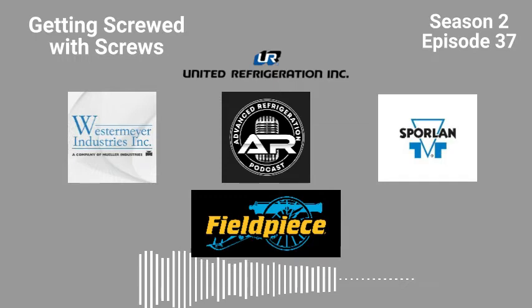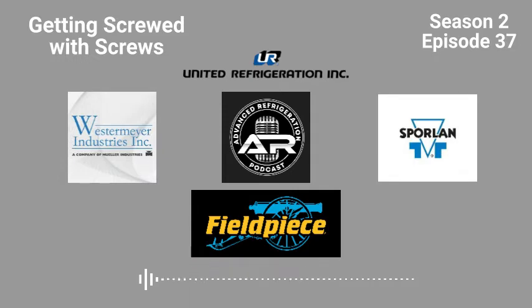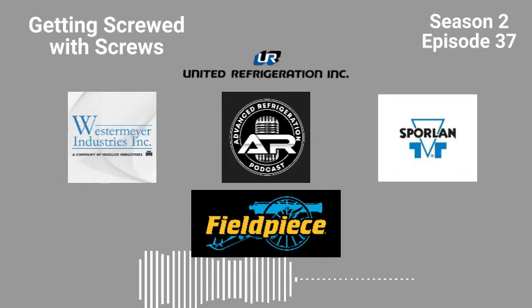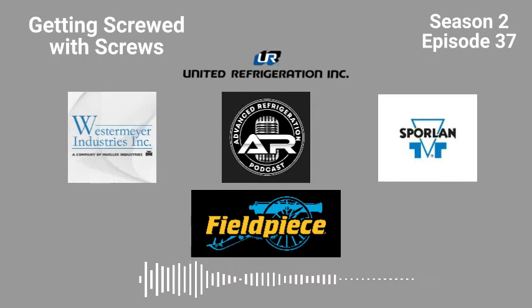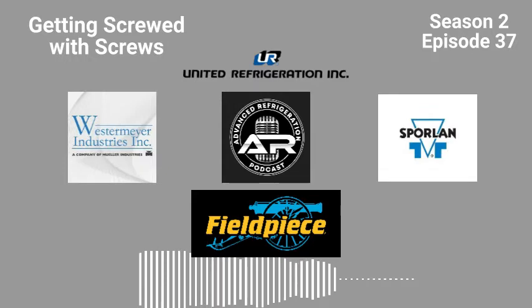So both compressors that were down, the one that was dead and the one that was down, were both 50 horses. Gotcha. So we're down 100 horsepower. This is a massive rack, by the way. Massive. I think it's 5 350s, and then a 65 and a 25. So you have a lot of volume and gas too. You probably have like a 3 1/8 discharge line. 4-inch. Yeah, it's massive. So at this point we're committed.